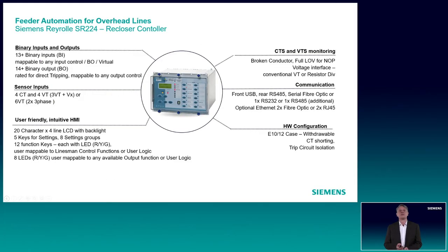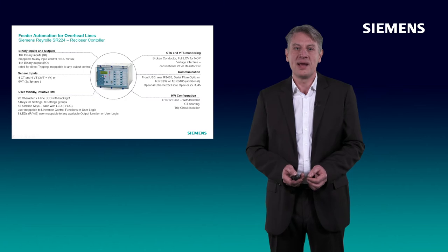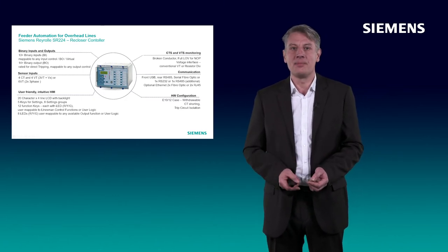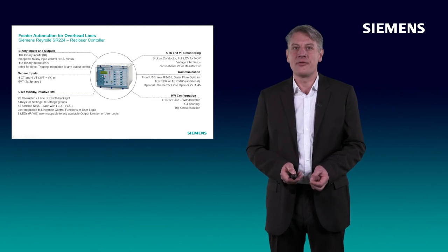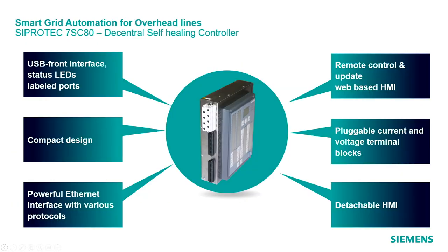Let's move to the second pillar: the feeder automation for overhead lines. The feeder automation system for overhead lines is mainly based on reclosers. Reclosers are circuit breakers which are pole-mounted. Recloser controllers take the action of the protective device. The Siemens Reyrolle SR224 is a perfect device for this kind of local automation on reclosers. It has the basic functionality needed for these applications, based on recloser cycles, six voltage inputs, and different curves and parameters for overhead line devices.